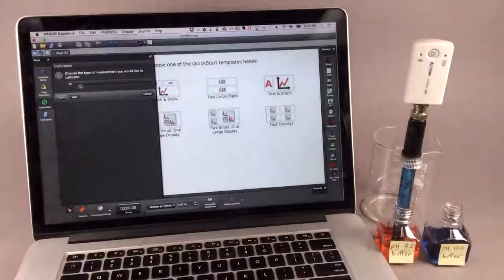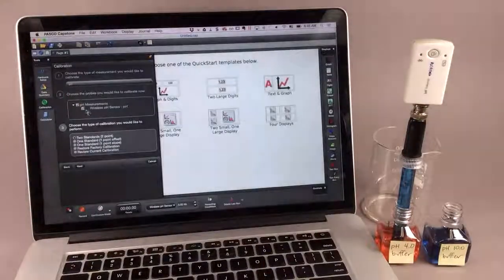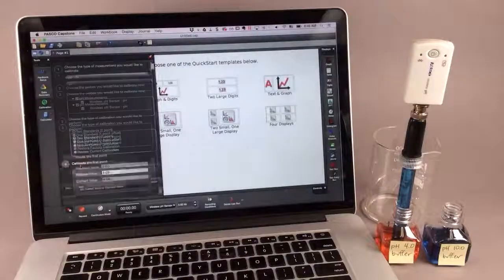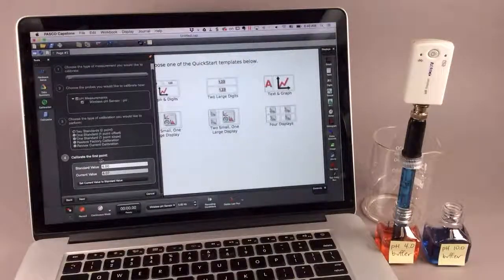Make sure that I've selected the pH measurement to be calibrated. Choose Next. Make sure that the pH sensor is selected. And I'm going to stick with the default 2 standards calibration for a 2-point calibration. I'll choose Next. And it asks me to calibrate the first point. I can type in the known pH. In this case, it defaults to 4, which is my known first pH.